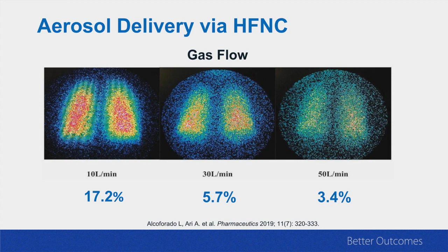Since gas flow has an inverse relationship with lung dose, our goal is to improve the delivery efficiency of the device during the treatment. Let's say your patient is going to use the high flow nasal cannula at 50 liters per minute. If you need to deliver an aerosol treatment to your patient, decrease the gas flow rate during aerosol therapy to improve the delivery efficiency of the nebulizer. That way, your patients can benefit from your treatment. However, you need to use this technique only if your patient is able to tolerate low flow rates. It shouldn't be a problem.